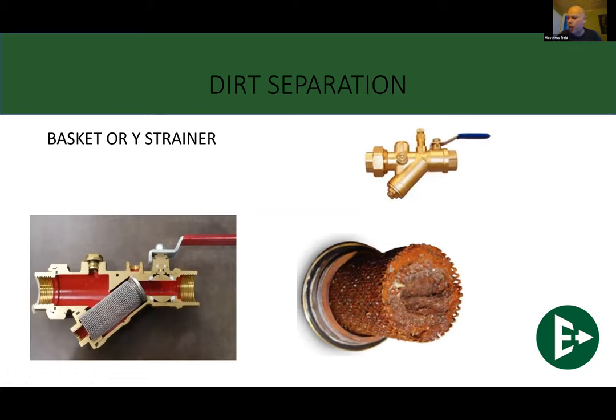Now, I make no qualms about it. I don't like these things. I don't like them at all. And there's a couple of reasons. Number one, as the water comes into these guys, first of all, it needs to get stuck in the basket in order for that particle to get caught. As soon as that particle gets caught inside of the basket, it starts to lose efficiency. You're not able to have much flow go through this guy now because it's got that particle caught inside of it. And in theory, the more efficient this thing becomes by catching more and more particles, you get a restriction on flow immediately downstream. So it's not a great way to get the dirt particles out of a system.